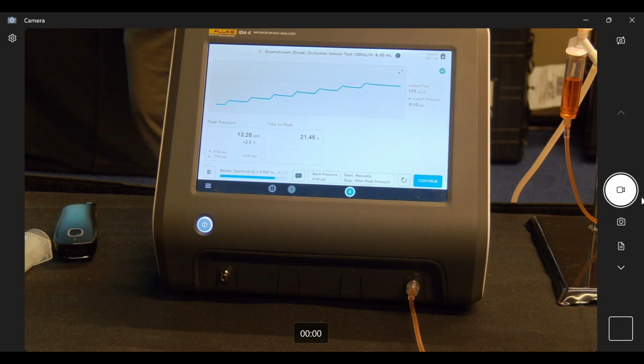And in 5 years, equipment doesn't fail like this - you don't see a drastic spike. What you'll see is like a hockey stick curve. You'll see static pressure outputs for a long period of time, and all of a sudden you'll see it, because you buy your entire fleet at one time usually, and they'll start to fail. So if you can take this analysis, take this information and run it over 5, 6, 7 years - the average life expectancy of a medical device, 7 years, right? If you can run this over 7 years and start to do some analysis, saying hey, what's my percent deviation after 5 years? And once you start to see a deviation, you can now move your program from responsive maintenance to predictive maintenance.